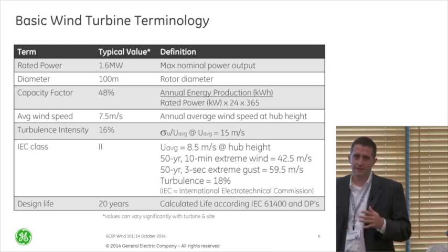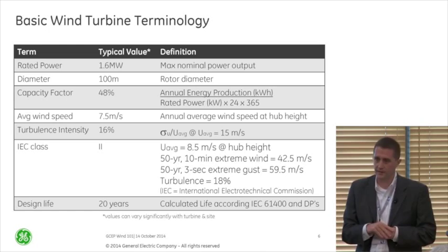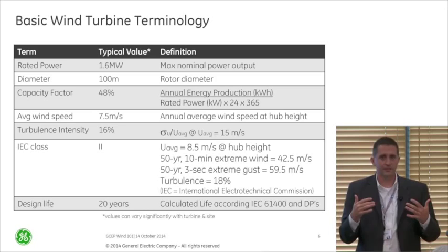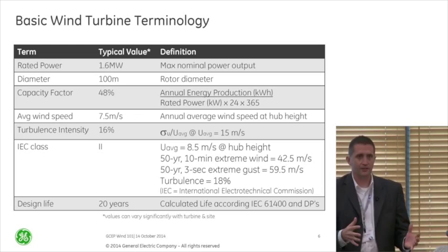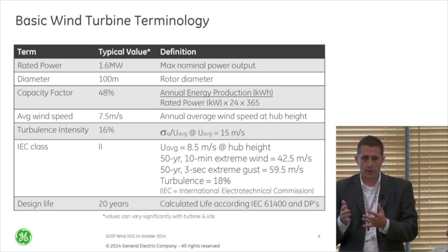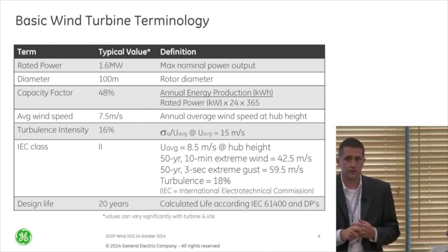Associated with that is some sort of turbulence intensity factor, which is important. We also have an IEC class — we design a wind turbine to an IEC standard, and they have different wind classes. An IEC class three has a wind speed of seven and a half meters per second; a class two is eight and a half meters per second. That's associated with distribution factors including maximum wind speed, maximum gust, and maximum average wind speed to design for.